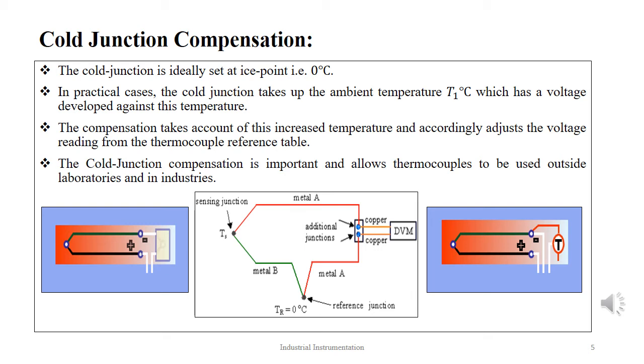Another temperature sensor is used to measure the temperature at the cold junction, and the corresponding junction voltage is looked up from the thermocouple reference table. This compensation then allows the electronic component in the device circuit to use the established thermoelectric voltage tables or polynomials to determine the temperature at the hot end. It is because of the cold junction compensation that thermocouples have now come out of the laboratories and are largely used in the industry setup.